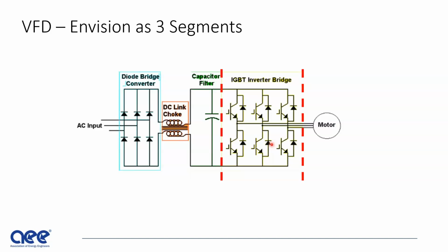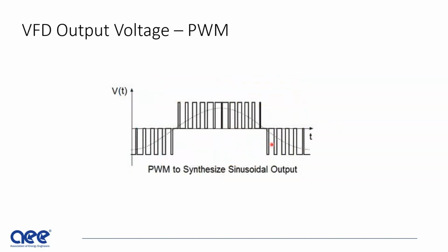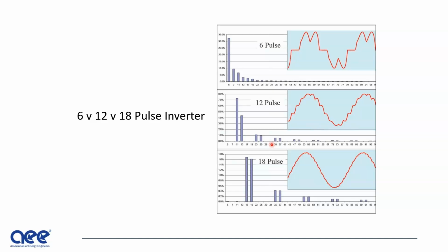This is the bridge that we're going to get into more details on. So in the bridge, a PWM, or pulse width modulated waveform, is used to synthesize a sinusoidal output. Now you can see these series of pulses, while they may roughly construct a sine wave, it's a terrible sine wave in terms of the fast dV/dt that you see on these pulses. Here you see the difference between the waveforms on a 6, 12, and 18 pulse. A 6 pulse only for the smallest motors because of the inefficiency of the heat that's generated. As you move up in power, you really need to clean up that sine wave and go with an 18 or even a 24 pulse to get the smoother waveform.